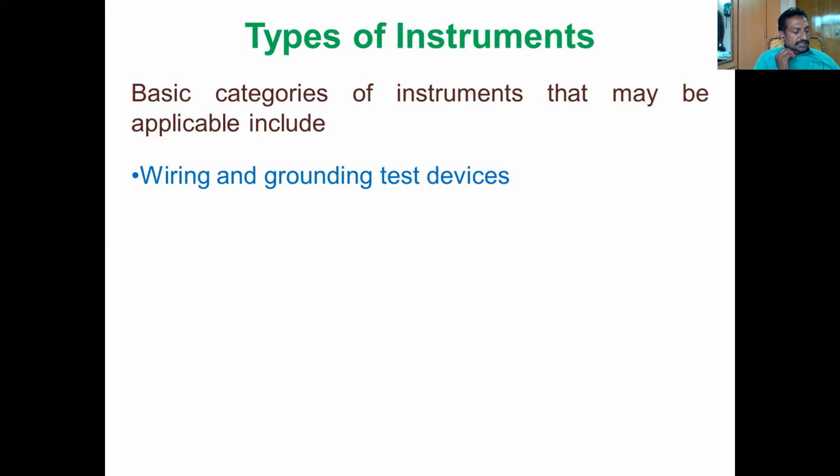First we'll see wiring and grounding. This applies to end users as well as substations. Many power quality problems reported by end users are caused by problems with wiring and grounding within the facility. These problems can be identified by visual inspection of wiring or grounding. So what to do? First, detect isolated grounds, shorts and neutral-ground wires. Separately, you have to identify neutral grounds as well as isolated grounds.